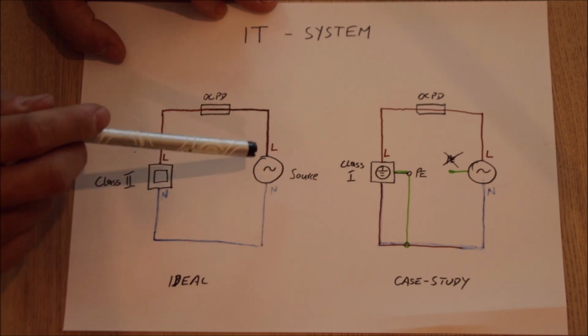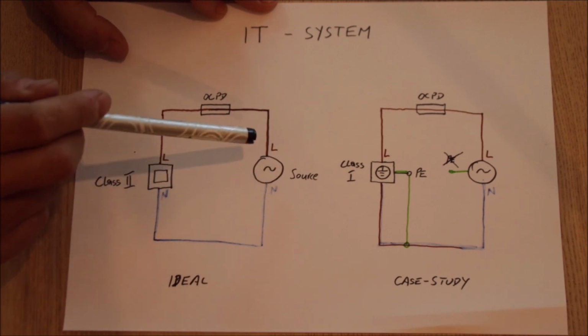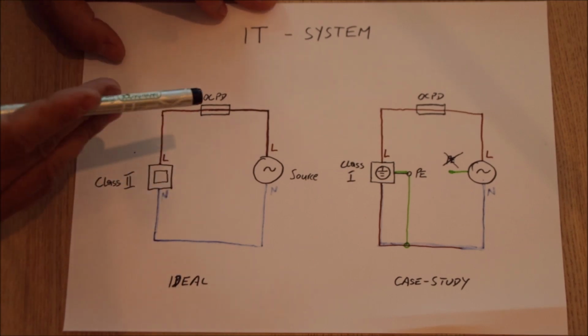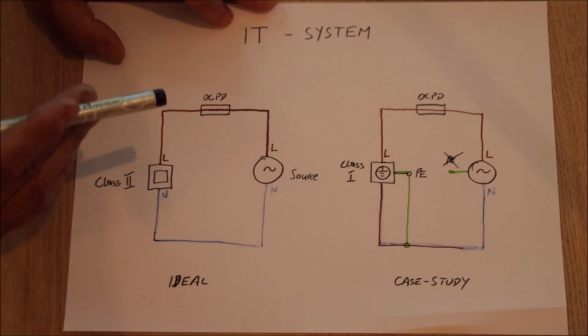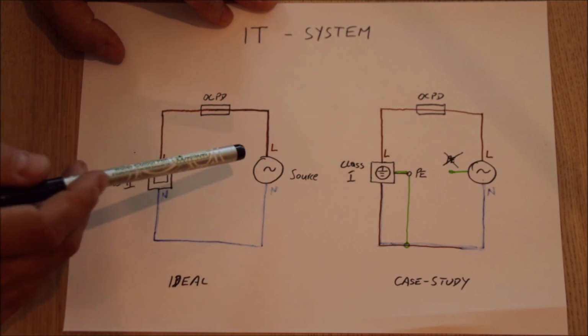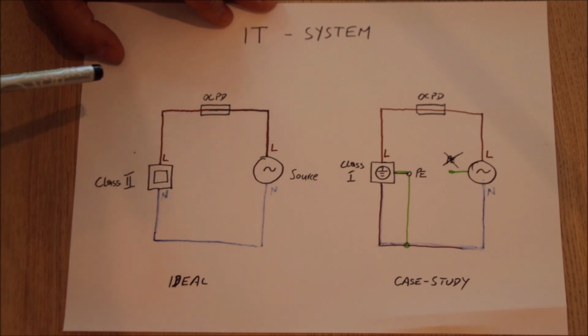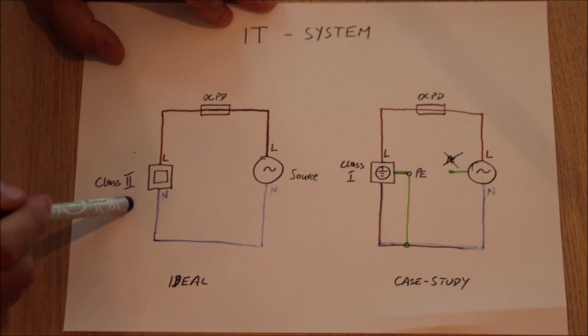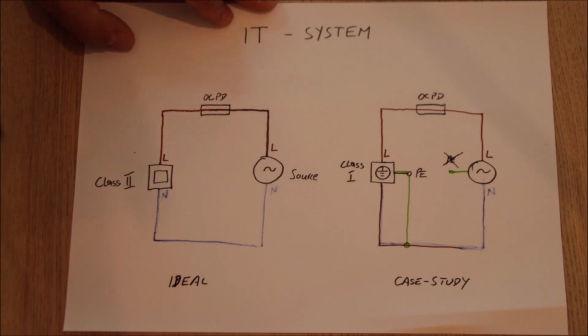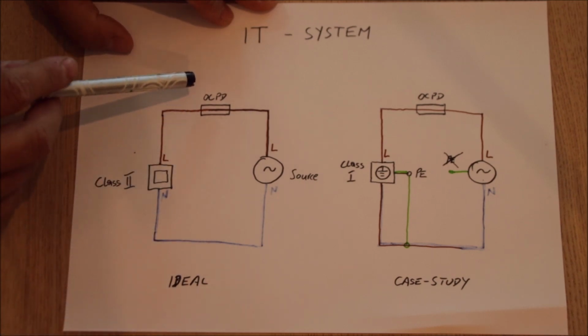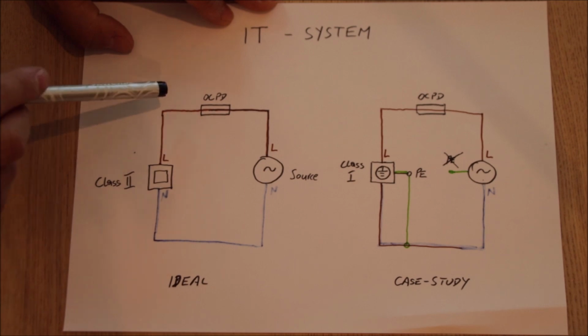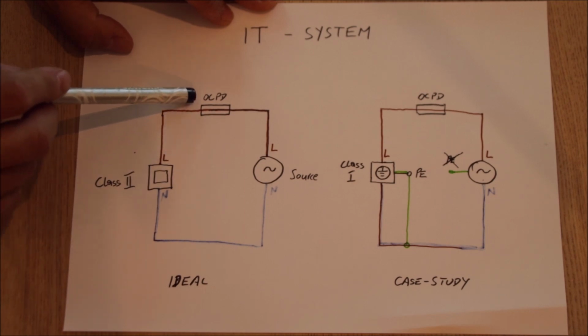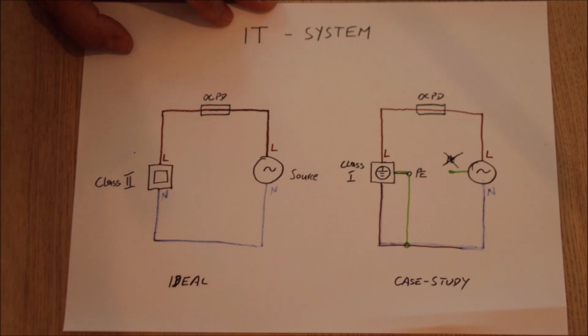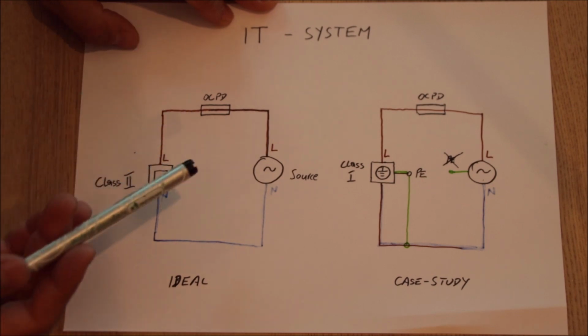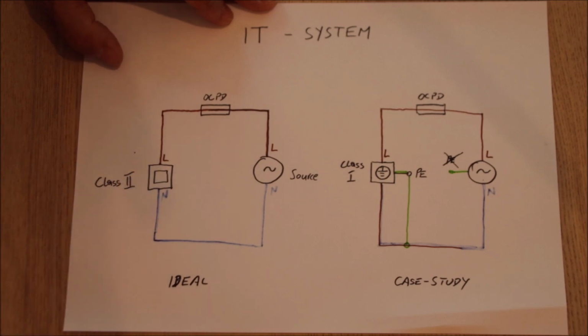You have the power source. We only have L and N. The wires there are perfectly separated, insulated, so that usually nothing can come in contact. We have our hot and we have our appliance, and the return path via the source neutral. There is one protective device present, and that is an overcurrent protection. So that might be an internal fuse, that might be a circuit breaker, etc.